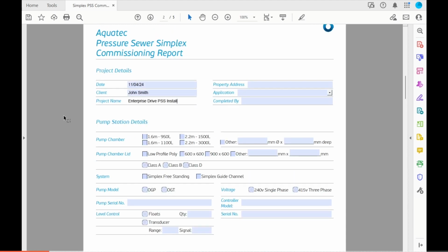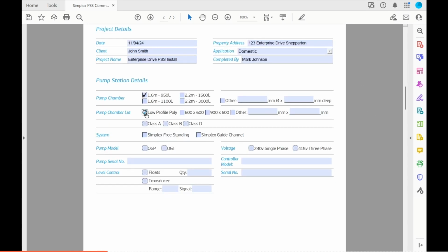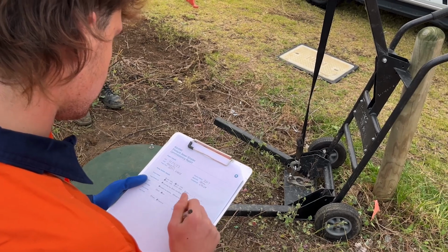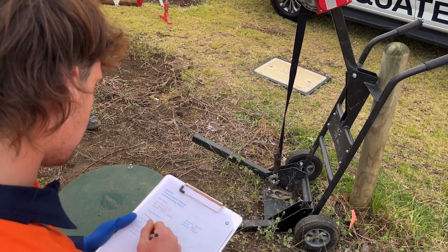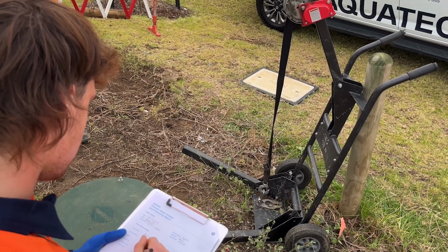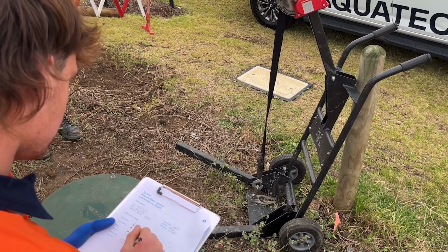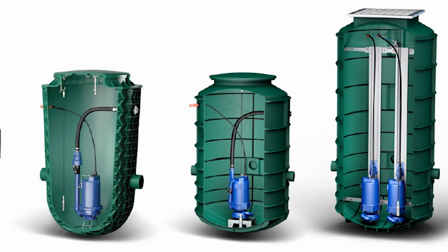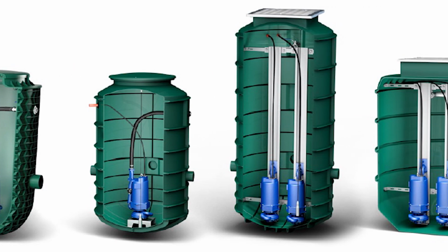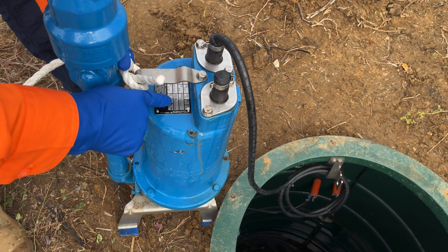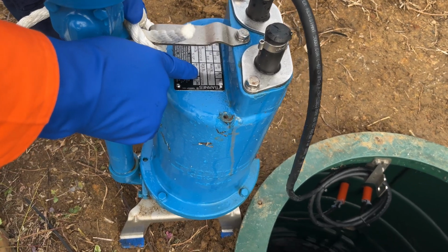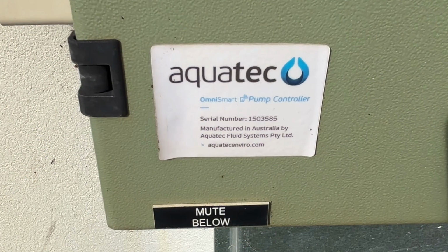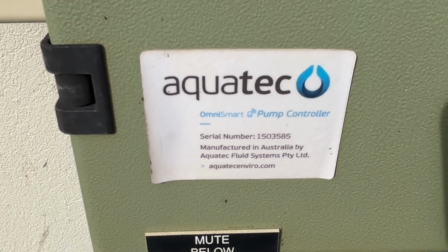After completing some basic information, you can move on to the pump station detail section to capture the dimensions of the chamber. This is critical information if pumps are changed and replaced in the future. Working through the form, we nominate what the system is, which is mostly just a tick box exercise with determining whether the system is a simplex, duplex, triplex, freestanding, or guide channel mounting type, pump and controller serial numbers, and all the unique details that this specific installation comprises of.